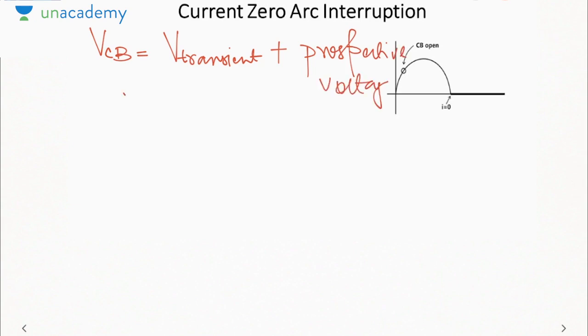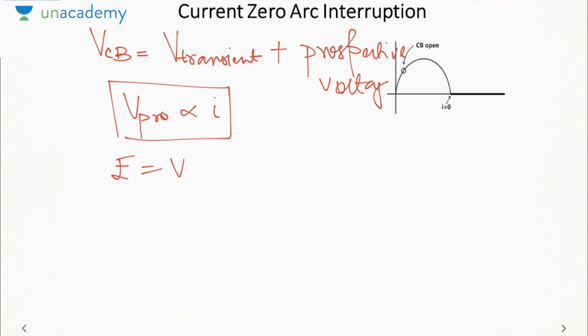Now this prospective voltage is proportional to current, due to which the voltage of the circuit breaker is increased. If the voltage across the plates increases, the electric field between the plates, equal to V by D, also increases, due to which the air will ionize.